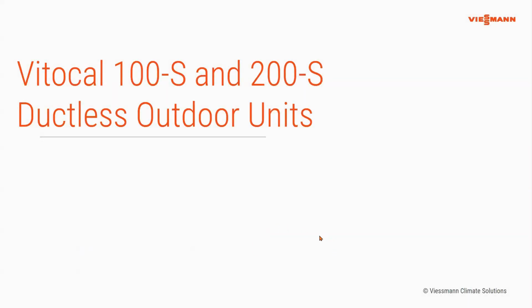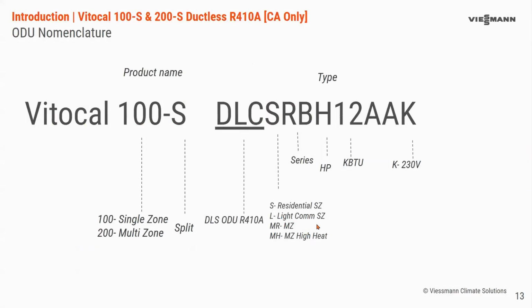So that was kind of an intro to the ductless lineup, and now we're going to talk a little bit more about the outdoor units themselves, starting off with the nomenclature. We talked about the 100S and the 200S, but just going over that a little bit more. The Vitocal is for our heat pump products. So we have the Vitocal air to water, and soon we will have a Vitocal water to air. However, after the Vitocal is where the model number will differentiate to let you know what type of product it is. So this is 100 for single zone, 200 for multi-zone. The S is always going to be there because this is a split system. The outdoor unit is separate from the indoor unit.